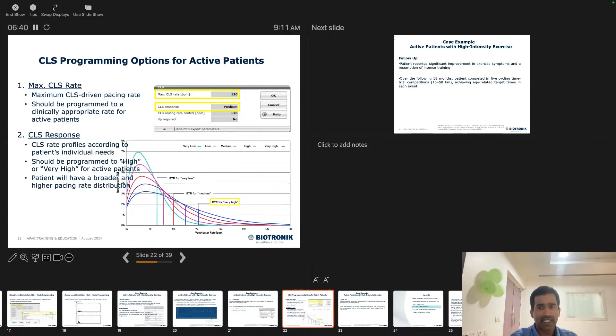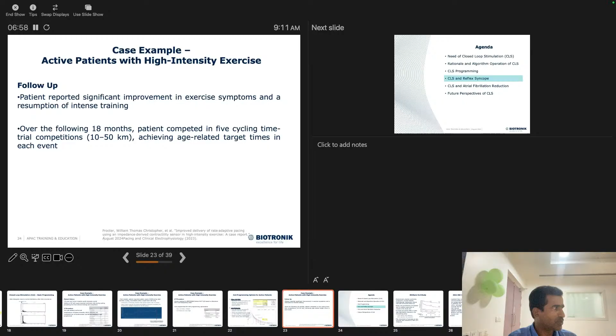Most of the rates would be at these rates when we program very high. When we program medium, the heart rate will be approximately around 80, so 70 to 80. When we program very low, it will be base rate plus 70, 75. So this is programmable in the programming parameters. For this patient, they've selected high, very high, and 160 as the accelerometer sensor rate. In the follow-up, the patient reported no symptoms of SOB and is relieved, and he is able to participate in a lot of cycling and athletics.